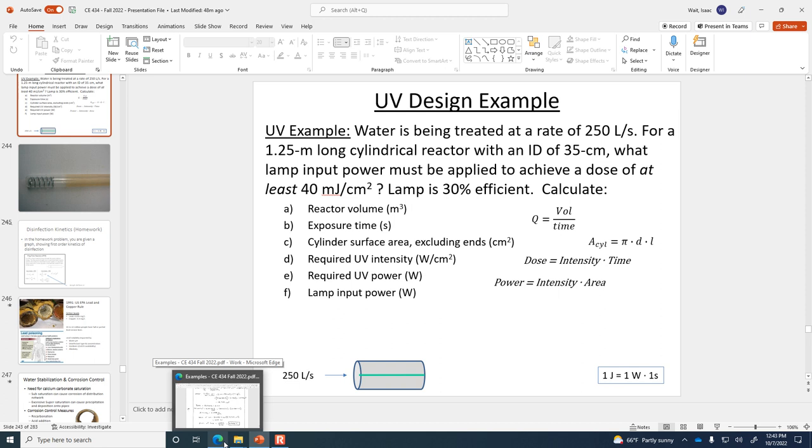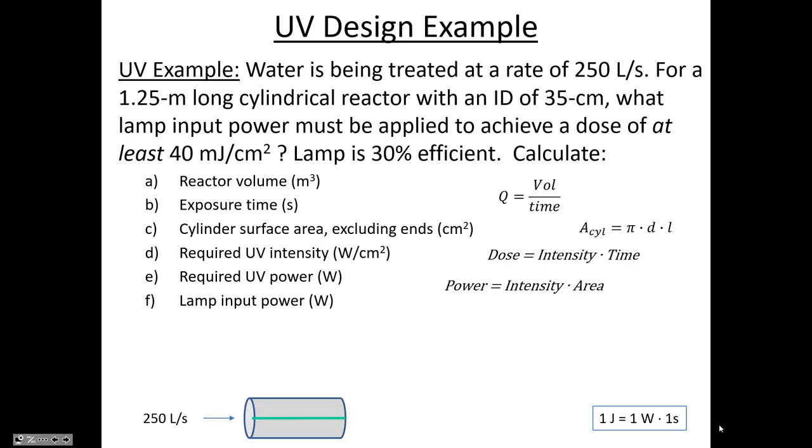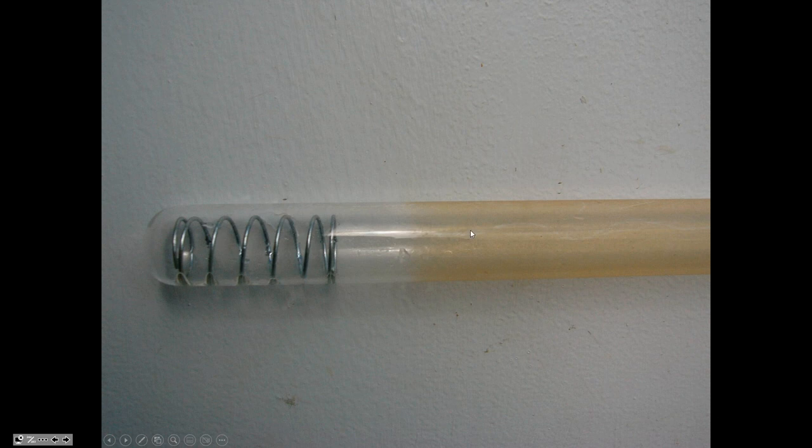I spent three years studying the fouling of these quartz sleeves. That was my PhD dissertation—the chemical reactions and the effects of when UV reactors have the quartz sleeves with mineral accumulation. There ends up being quite a lot of different stuff that can put itself onto the surface of these sleeves and how the performance, obviously if the intensity of the light is lower, then there's not going to be as much disinfection going on. Let's move on to talking about corrosion.